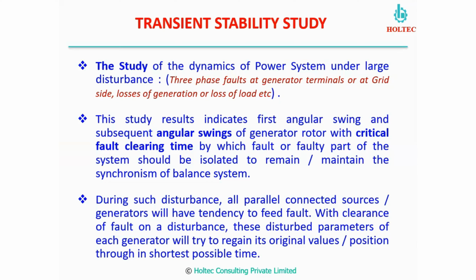During such disturbances, all sources are connected in parallel, so everybody has a tendency to feed the fault. When we clear this fault disturbance, the parameters of each generator will try to return to their original position in the shortest possible time. If the stability is ensured, then every generating set will come back to the normal steady state condition. If the transient stability fails, then your generator will trip.